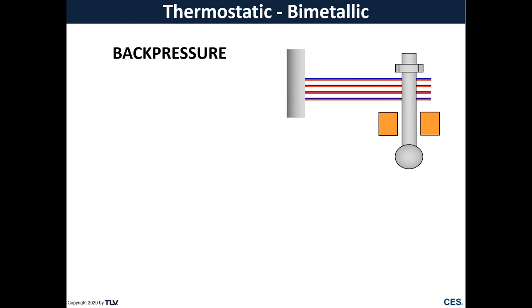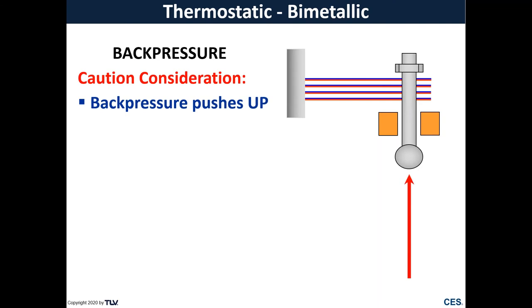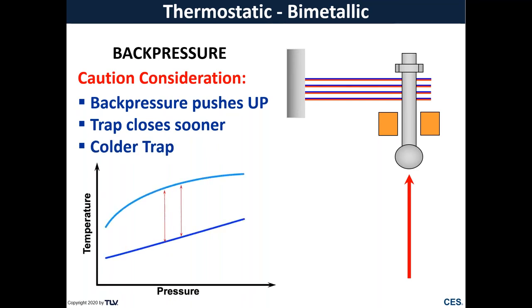Last thing to consider with this downstream valve head design is back pressure is going to help those bimetals close this trap. And so as you increase back pressure, it's actually going to be pushing up against that valve head, closing that trap quicker than what it normally would, ultimately resulting in a further degree of subcooling in your condensate.